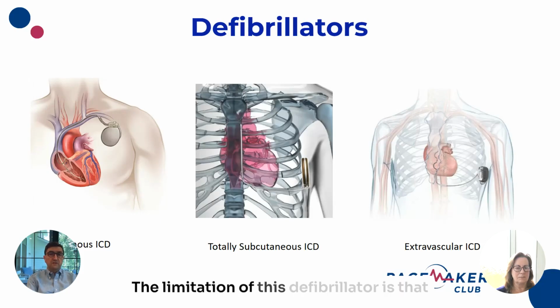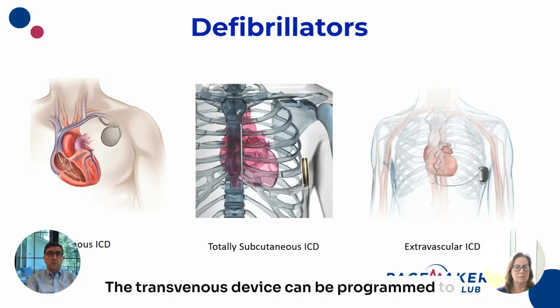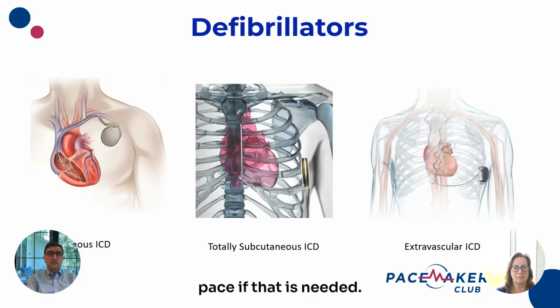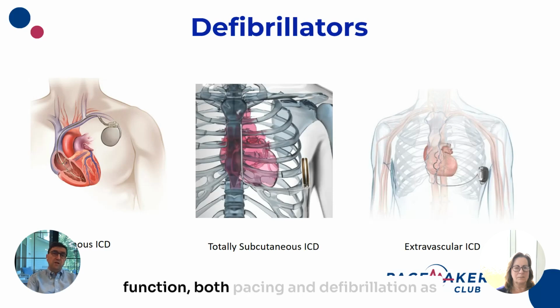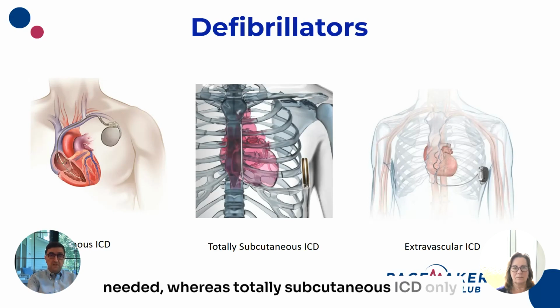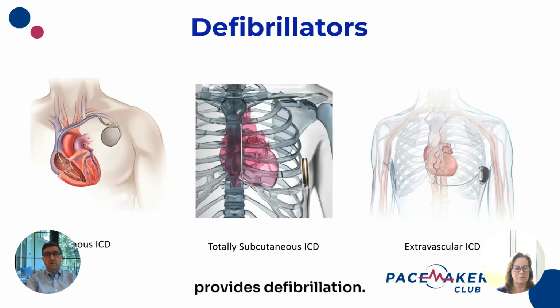The limitation of this defibrillator is that it cannot pace. The transvenous device can be programmed to pace if that is needed. So the transvenous ICD really has dual function, both pacing and defibrillation as needed, whereas the totally subcutaneous ICD only provides defibrillation.